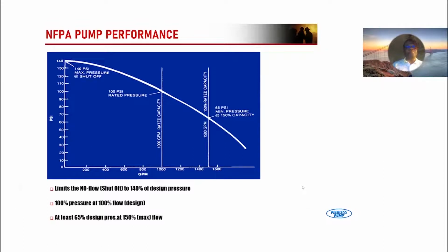And this is very important because this is the steepest shape the curve can have, but our curves at Peerless are a lot flatter. Especially when you're looking at inline pumps and split case pumps, most of our shutoff heads probably range between 110 and 120% of the design, which is very good when you start looking at your piping pressure and things like that. It helps a lot in trying to minimize additional valves for pressure reducing. So that's the PEERLESS pump design.